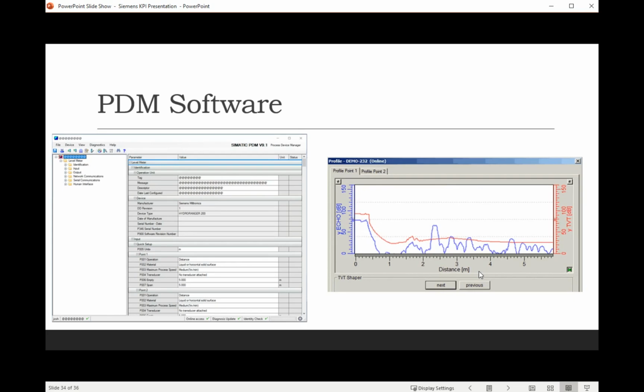It also gives you access to see the echo profile in the older style Hydrorangers as well. With a new HMI you can see it on the screen, but on the older style you have to have PDM software in order to see what's going on and take a snapshot. Another thing PDM software can do is get all the parameters from the Hydroranger and put them into a PDF, print them out, and put them next to the Hydroranger, so that you have a record of all your parameters in that Hydroranger. Some of these Hydrorangers have settings for relays or for pump control that are difficult to remember. So this gives you the ability to print everything out, put a copy right there, and have a record of it. You can also save a copy of the parameters onto your laptop.